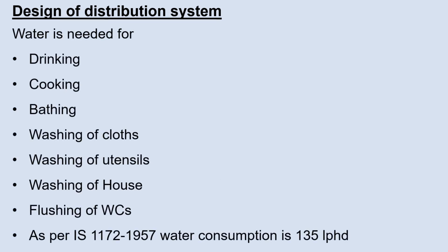Water is needed for drinking, cooking, bathing, washing of clothes, washing of utensils, washing of house, flushing of the water closets, and as per IS 1172/1957, water consumption is 135 liters per head per day.